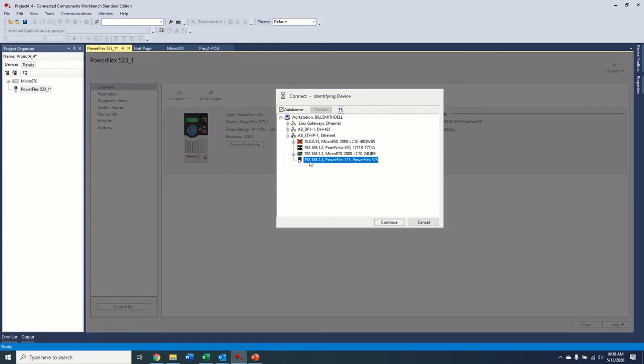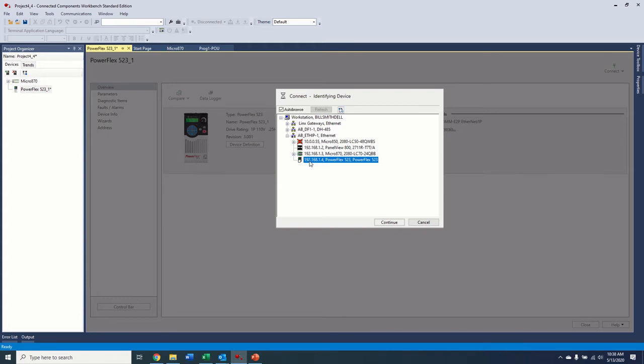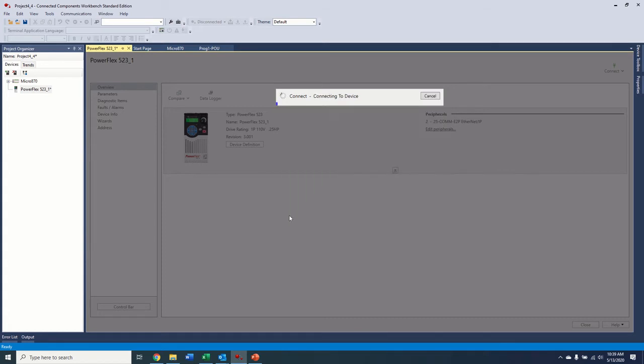Or you can put the IP address in using the parameters on the drive and the HIM module. So you put your IP address and your subnet mask in that way. And then you can come to this step and program the rest of the drive. You can also BOOTP these drives using the old BOOTP method. And you can also go in over a serial connection using the drive serial or USB to serial DPI link. But in this case, my drive already has an IP address. So here we go. I know that my drive is .4. It's shown up in my RSLinx. So I'm going to hit continue.